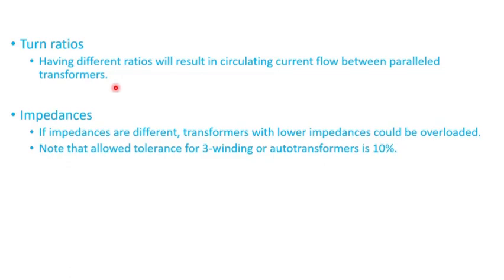Then if the transformers have different impedances, the transformers with lower impedances would have most of the loading, and in some cases they could be overloaded. As we will see in some examples, it just depends on the load they're serving. Just keep in mind when we say the transformer has seven percent impedance...